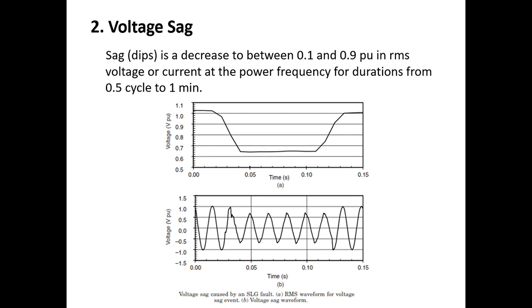If you see the second diagram, diagram B, it shows voltage sag caused by an SLG fault, that means a single line to ground fault. It shows the RMS waveform of the voltage sag event, and B is the voltage sag waveform. If you see the waveform from 0.05 to 0.1, you get a change in the amplitude, and that is called voltage sag.